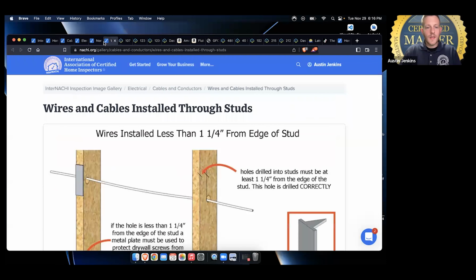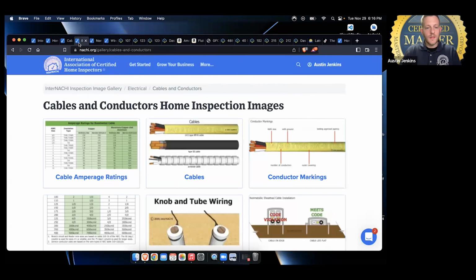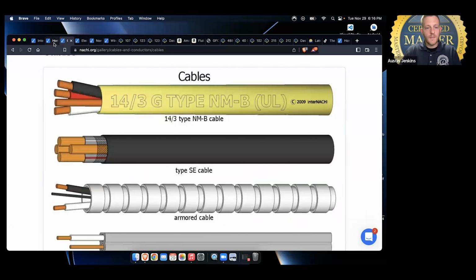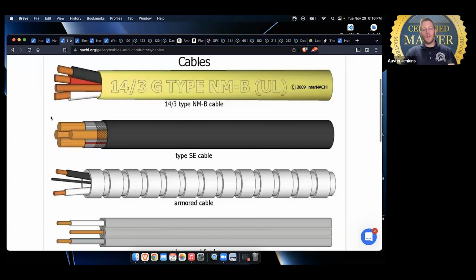I thought I had a diagram, maybe I deleted it because it didn't really apply. On a normal residential inspection, you're going to see two of these cables: your service entrance cable coming into the actual panel itself. Depending on when the house was constructed, you may see some old rag wrap cabling or cloth insulated wiring, but for reference we're just going to go with your standard Romex.